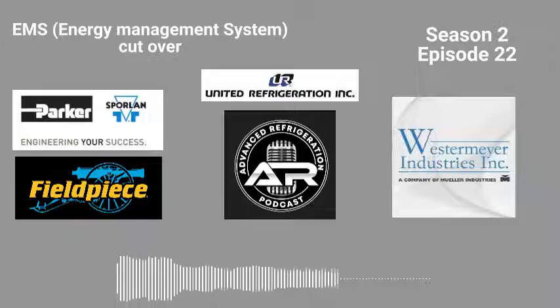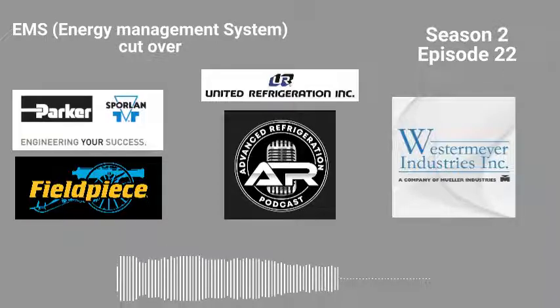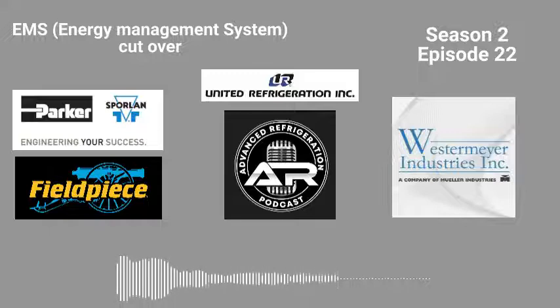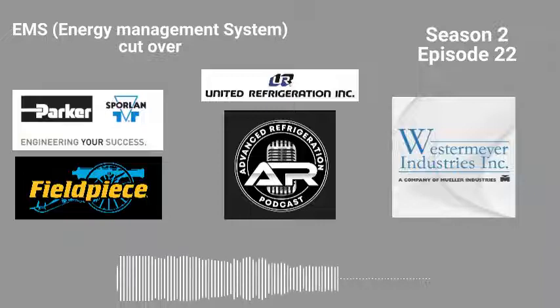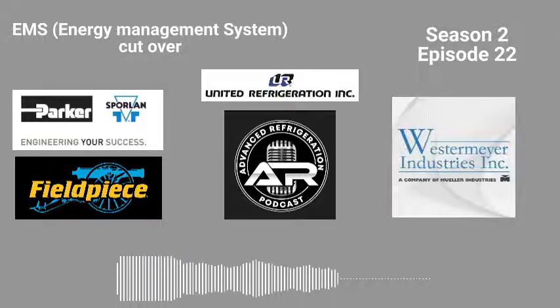One thing I love about the new Micro Thermo is you can print the I/O schedules right off the boards — inputs, outputs, board markings, everything is done for you. I'll save to a flash drive, take them home, print them, laminate them, and put them in the rack. The program is already in the board, so you can access it and it'll download whatever you have programmed as a PDF I/O sheet. So you pre-program it, print out the PDF, and that's your pop sheet.